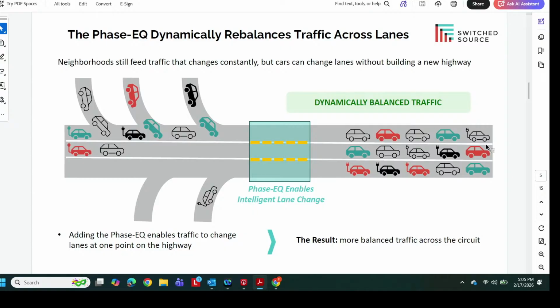The benefits of this are making sure you don't overload any individual phase. If you overload phases, you can damage equipment, and you get what we'd call nuisance trips, where the system thinks there's a fault but it's really just heavy load on one phase. It also limits your ability to reconfigure the grid for reliability purposes, like switching customers around or bringing more load back online after a storm.